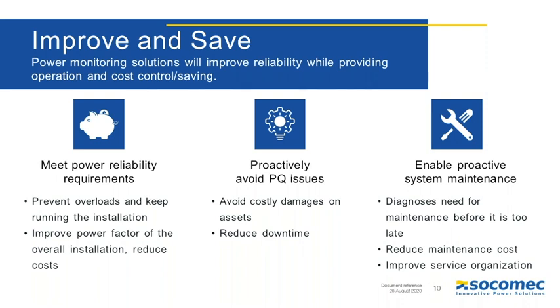The third one is that you can be proactive with system maintenance while using power monitoring devices, because you're able to monitor specific parameters of your loads and set alarms once they reach a certain level that you set yourself. This allows you to be proactive instead of reactive when an issue occurs.